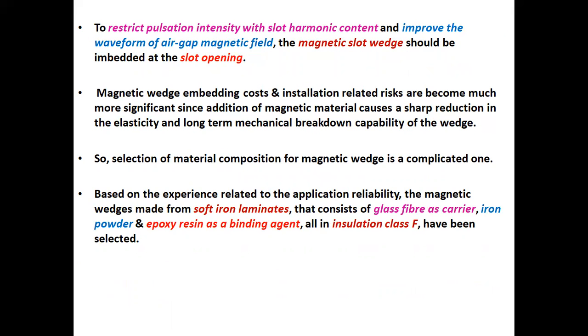To restrict pulsation intensity with slot harmonic content and improve the waveform of air gap magnetic field, the magnetic slot wedge should be embedded at the slot opening. Magnetic wedge embedding costs and installation related risks become much more significant since addition of magnetic material causes a sharp reduction in the elasticity and long-term mechanical breakdown capability of the wedge.